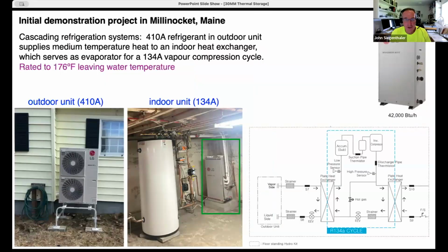Yeah, these systems are using a kind of unique air to water configuration. I call it a cascading system. Basically, the outdoor unit you see on the left there, that's a standard outdoor condenser unit running on R410A. And that has a refrigerant line set that goes inside and it goes to a box. You can see it in the middle photo there. That's actually another heat pump. So there are two complete heat pump cycles involved here. The first one lifts the outdoor temperature to an intermediate temperature. And then that refrigerant goes in and serves the evaporator of the indoor unit.